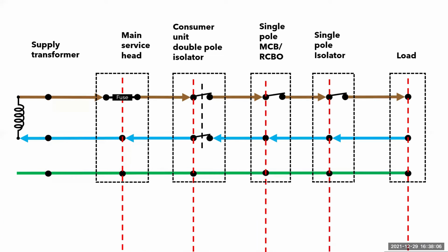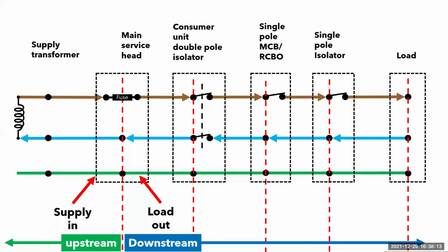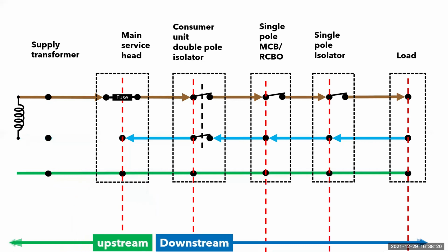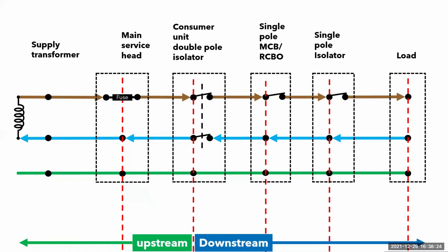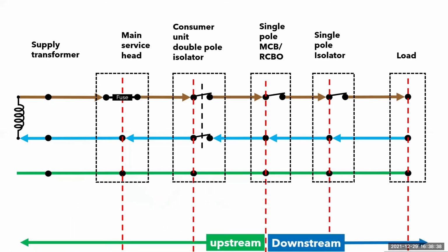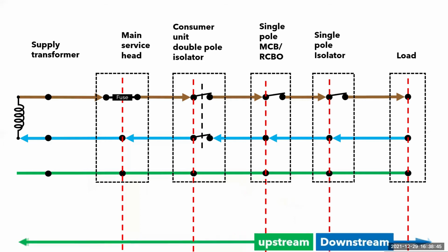Here we have the supply coming into the enclosure, originating from upstream, and the load coming out of the enclosure and heading downstream to the next enclosure. Just remember the source or supply is always upstream, just like the flow of a river. As we move downstream, what was the load from the previous enclosure is now the supply to the next, and the load is always coming out of the enclosure downstream. As this continues, as we move downstream, the supply is upstream and the load is downstream. Same again, supply is upstream, the load is downstream. Finally, we get to the end of the circuit, which is usually the appliance or point of load.